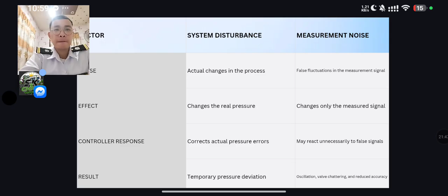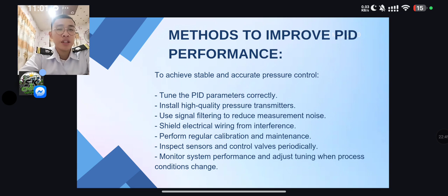Next, I have here the methods to improve the PID performance. To achieve stable and accurate pressure control, you must tune the PID parameters correctly, install a high quality pressure transmitter, use signal filtering to reduce measurement noise, shield electrical wiring from interference, perform regular calibration and maintenance, and inspect sensors and control valves periodically. Also, monitor system performance and adjust tuning when process conditions change.